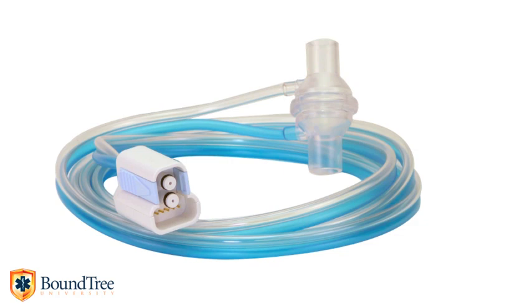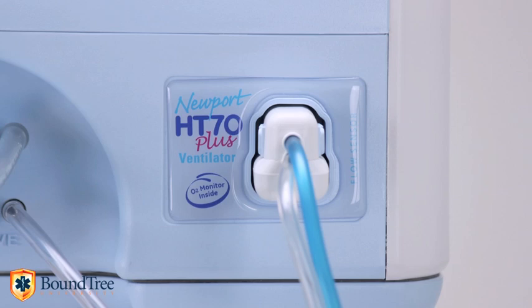The HT70 Plus can be used with or without the on-airway flow sensor. When the flow sensor is installed, the Plus provides airway regulation of volume delivery, exhaled rather than inhaled volume monitoring alarms, and flow triggering.